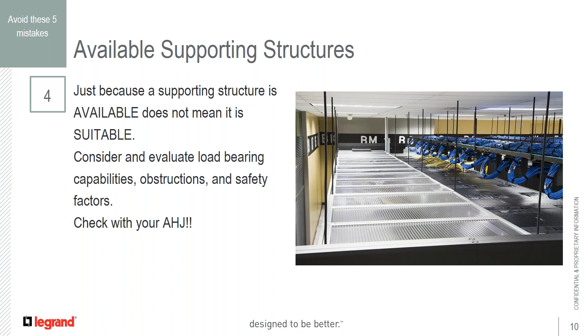Something else to take into consideration: when using the anchoring points and installing the containment, especially when supporting from overhead, will your supporting structures or threaded rods or whatever means you use interfere with other things in the data center, such as overhead cable tray, fire suppression, and are you violating any safety rules that may cause changes and confusion afterward? Best rule of thumb, always check with your authority having jurisdiction.